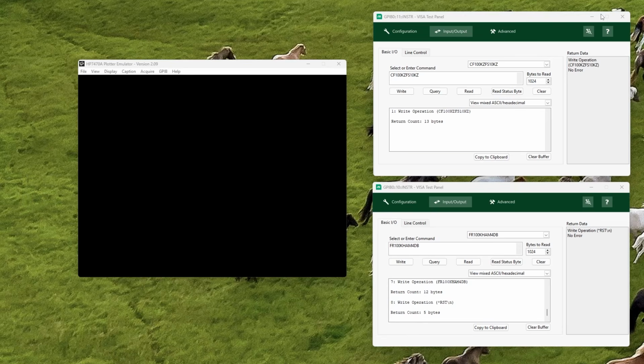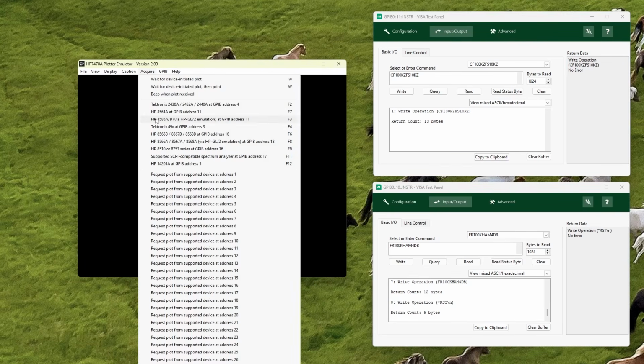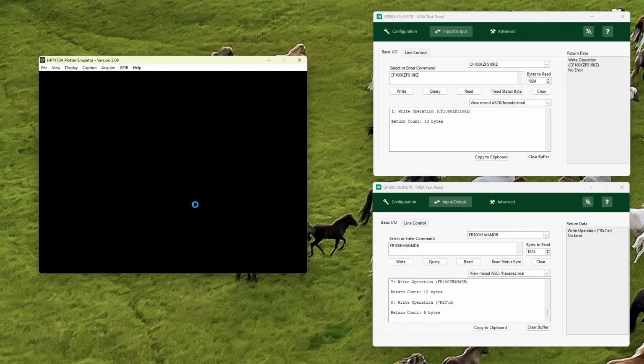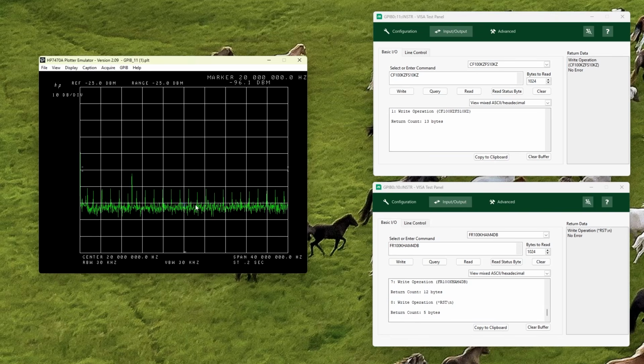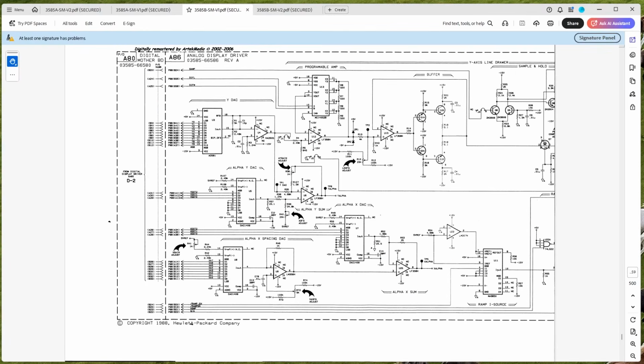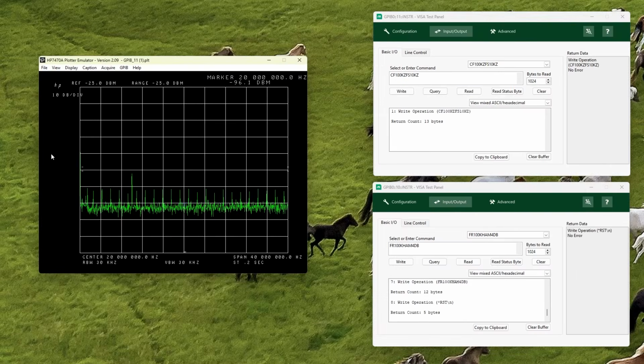so I have this set up, the unit is turned on, it is plugged in, and with KE5FX's tool, we can go in and acquire a plot from the unit at GPIB address 11, which is the default address and what the unit is in fact set to. So let's go do that. And there we go. We've got the unit set up. We're pulling a thing. So that's good. What that sort of means is that the display driver circuitry is basically working because we can do that.